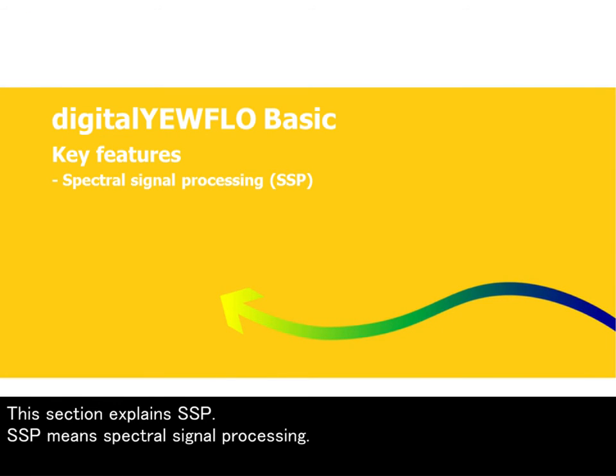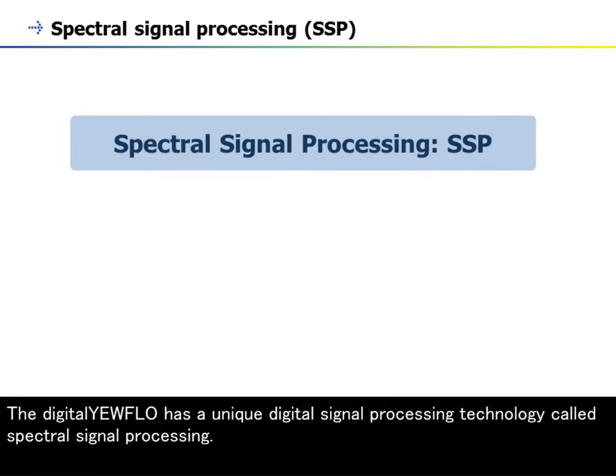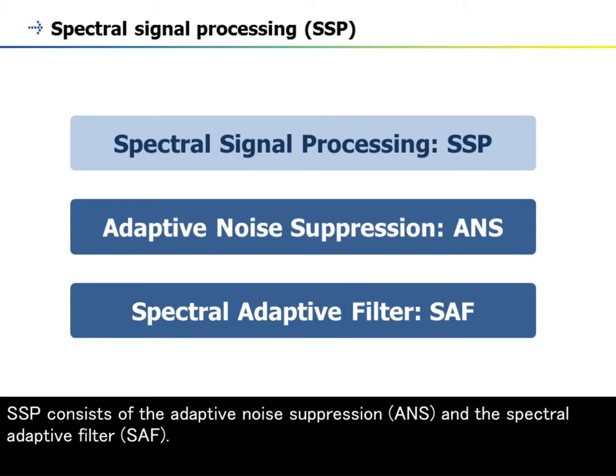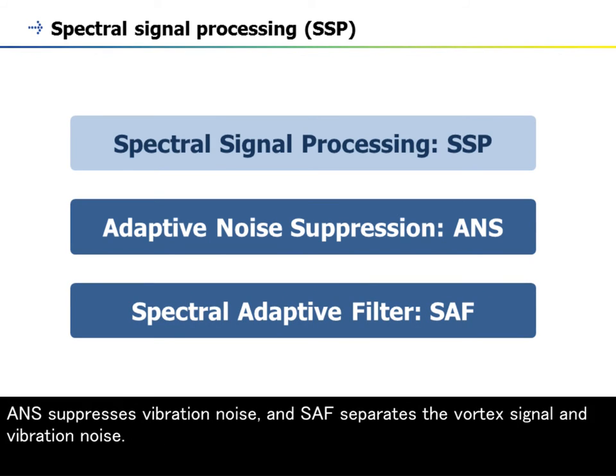This section explains SSP. The digitalYEWFLO has a unique digital signal processing technology called spectral signal processing. SSP consists of the adaptive noise suppression, ANS, and the spectral adaptive filter, SAF. ANS suppresses vibration noise, and SAF separates the vortex signal and vibration noise.